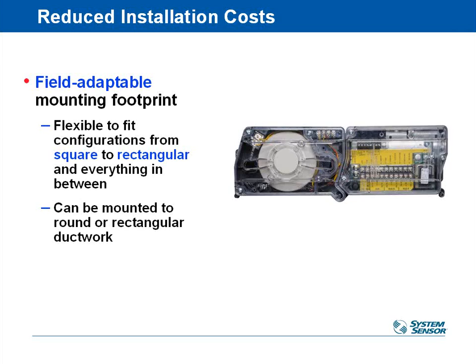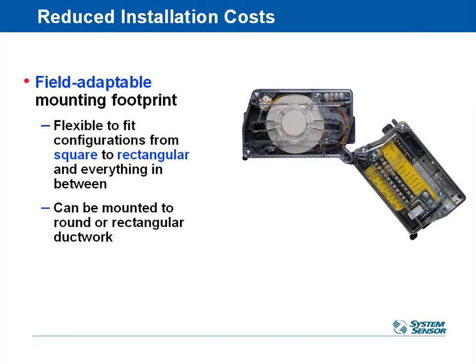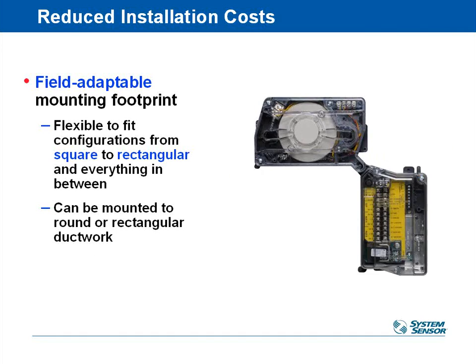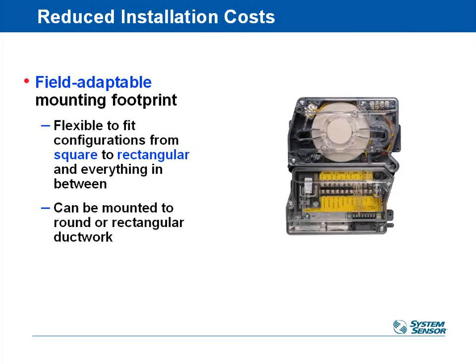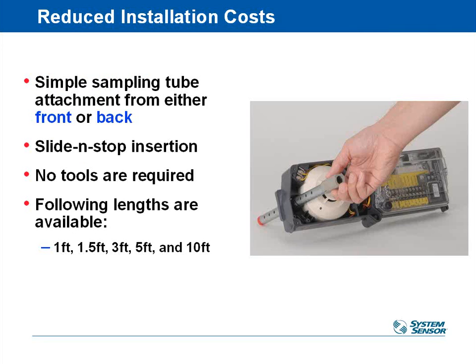This is one of the coolest aspects of this product here. Most of the time you buy a detector that looks like this. It's a rectangular shape. It fits where you put it. Everything's fine. Sometimes you have a tight constrained space and it doesn't fit, and then you got to go out and buy a different smoke detector to make it fit. Well, this one actually can field convert. You just take a screw out of the top, and then it flips over on this hinged access here into a square pattern, and then you put the screw back in. The wiring inside the hinge stays wired, so literally all you're doing is popping one screw out, flipping it, putting that screw back in, and now you can go ahead and mount this guy. So it does allow you some flexibility in terms of installation, hence the reason it's called Innovair Flex.